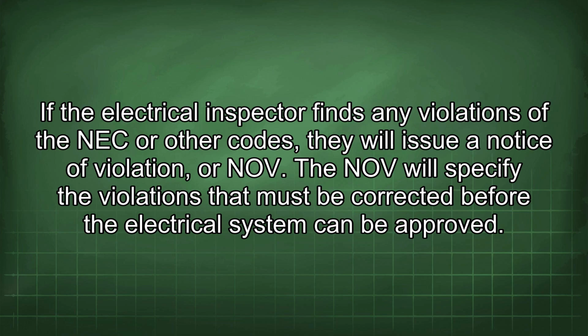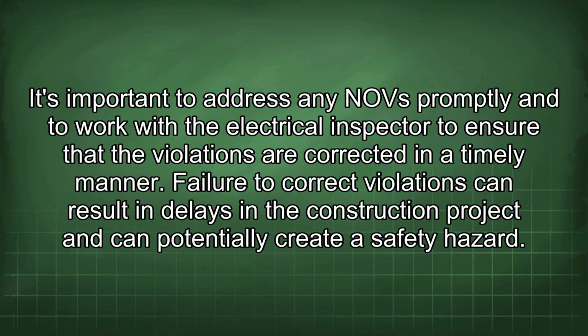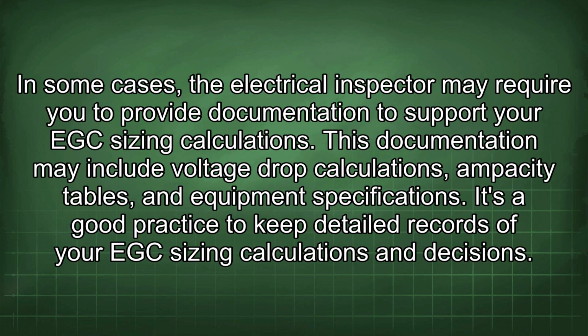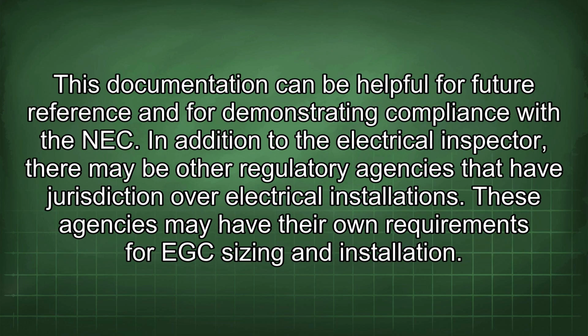If the electrical inspector finds any violations of the NEC or other codes, they will issue a notice of violation, or NOV. The NOV will specify the violations that must be corrected before the electrical system can be approved. It's important to address any NOV promptly and to work with the electrical inspector to ensure that the violations are corrected in a timely manner. Failure to correct violations can result in delays in the construction project and can potentially create a safety hazard. In some cases, the electrical inspector may require you to provide documentation to support your EGC sizing calculations. This documentation may include voltage drop calculations, ampacity tables, and equipment specifications. It's a good practice to keep detailed records of your EGC sizing calculations and decisions. This documentation can be helpful for future reference and for demonstrating compliance with the NEC.